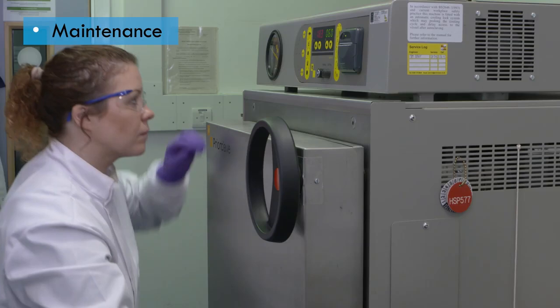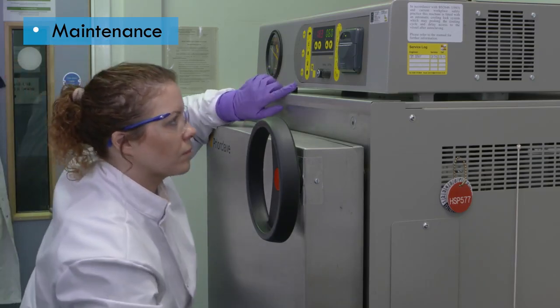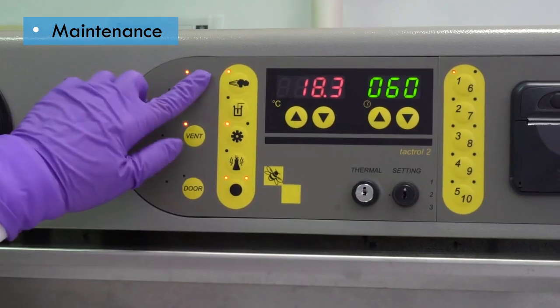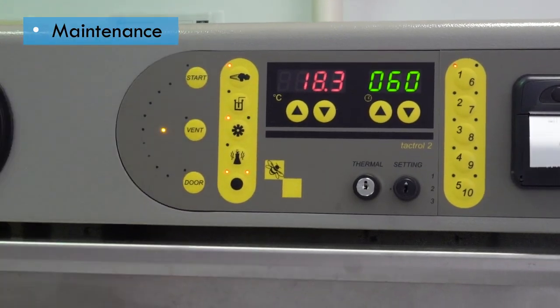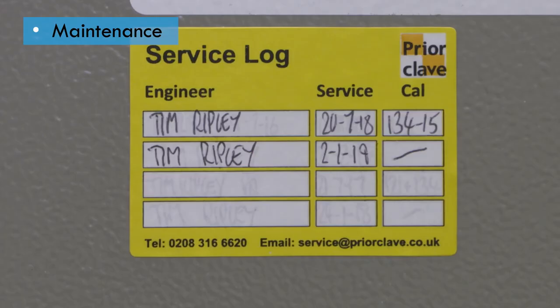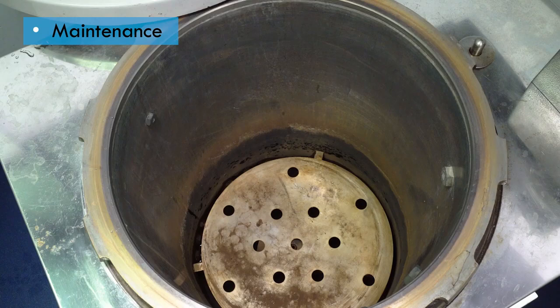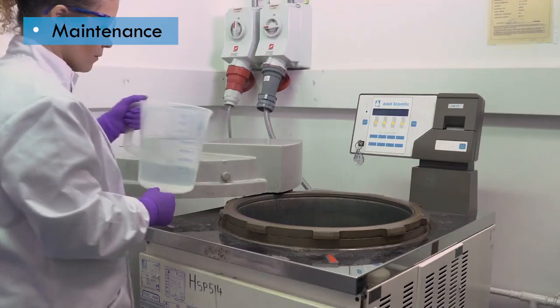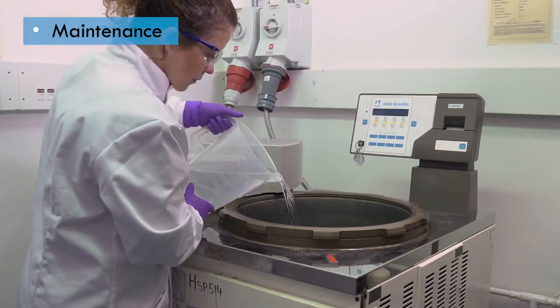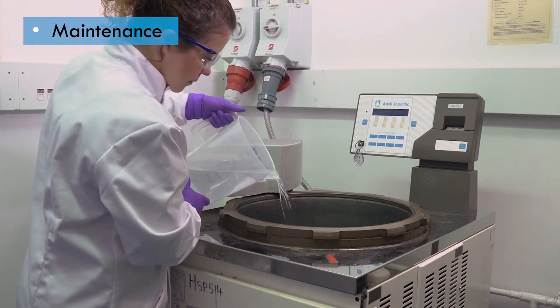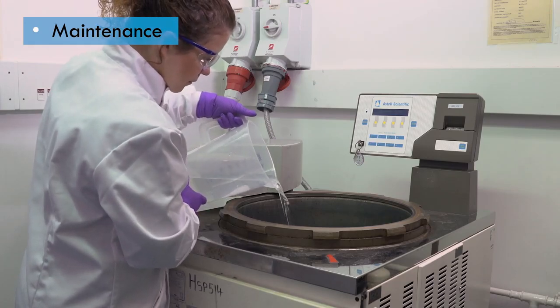Autoclaves must be well maintained to make sure they perform as required. This increases productivity and reduces downtime. Routine in-use maintenance includes making sure any water reservoirs are kept clean and filled with water, and are regularly checked for signs of wear and tear, such as corrosion.